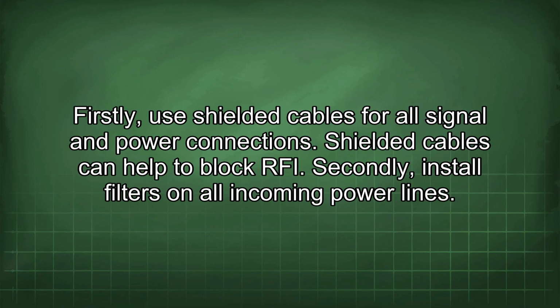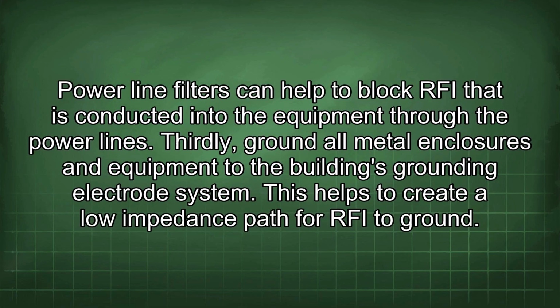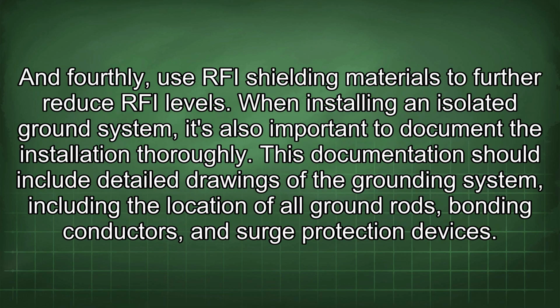Firstly, use shielded cables for all signal and power connections. Shielded cables can help to block RFI. Secondly, install filters on all incoming power lines. Power line filters can help to block RFI that is conducted into the equipment through the power lines. Thirdly, ground all metal enclosures and equipment to the building's grounding electrode system. This helps to create a low impedance path for RFI to ground. And fourthly, use RFI shielding materials to further reduce RFI levels.